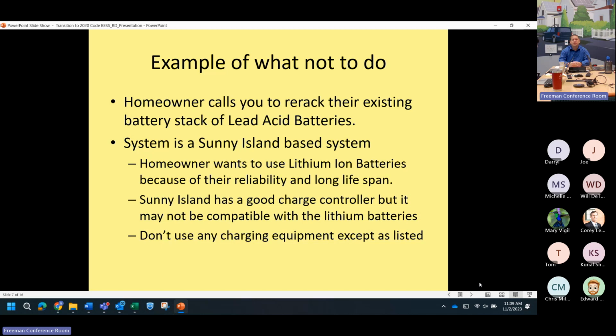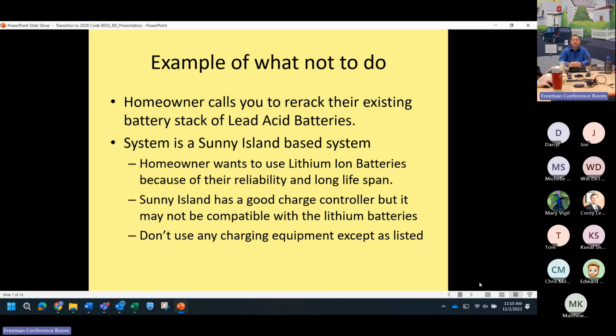Although Sunny Island has a good charge controller, and I'm picking on Sunny Island today, don't use the charge controller unless you know it's compatible with those types of batteries. It's going to have to be listed, basically. Don't use it unless it's listed to do it, because you are the one putting the risk of fire into the situation if you do that.